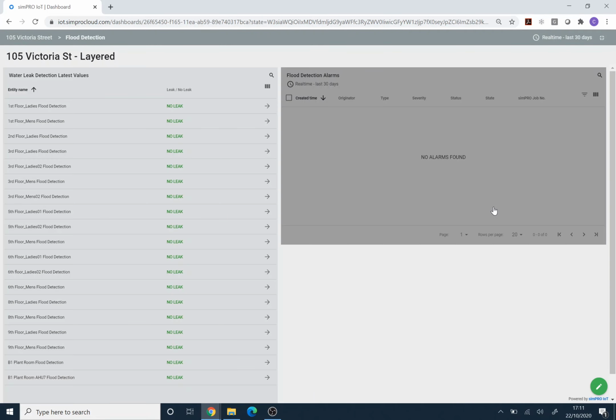For this requirement, we have installed over 25 of our unique H2O nodes across the bathrooms of the building and various other zones. These devices, the size of a large watch and running on a coin cell battery for multiple years, send an immediate alert in the event of water detected. Luckily at this stage we can see no flood hazards active on this particular building. Due to the lack of wiring and cabling, these units can be installed and were installed in a matter of hours across the site.